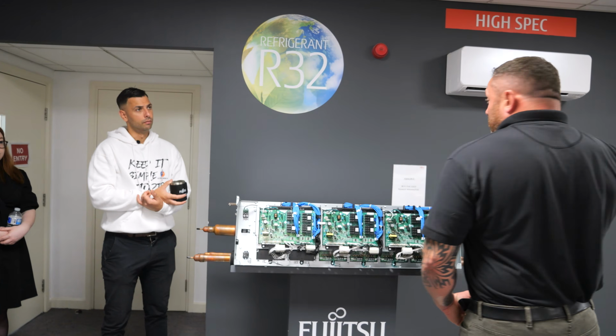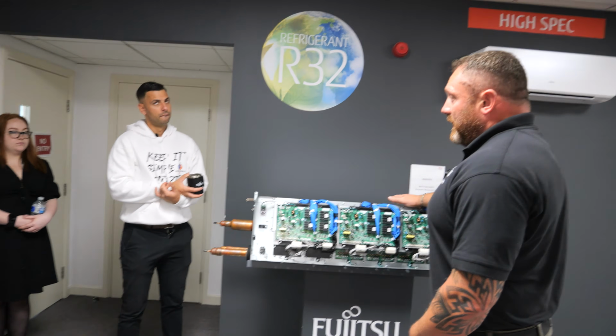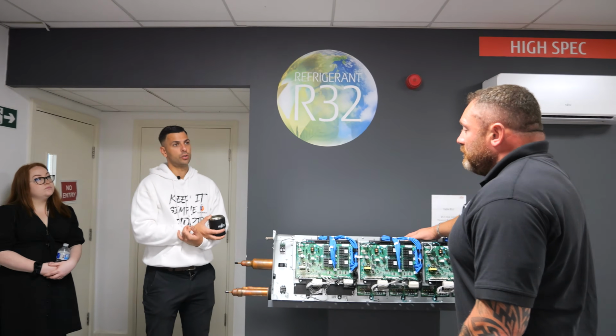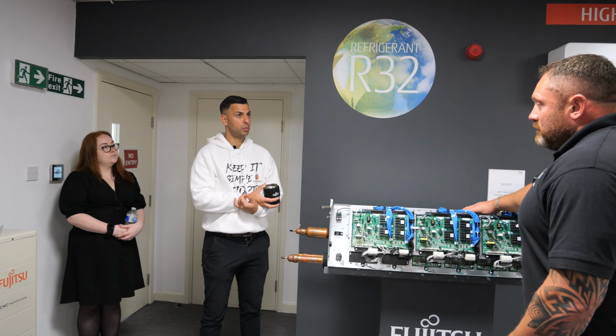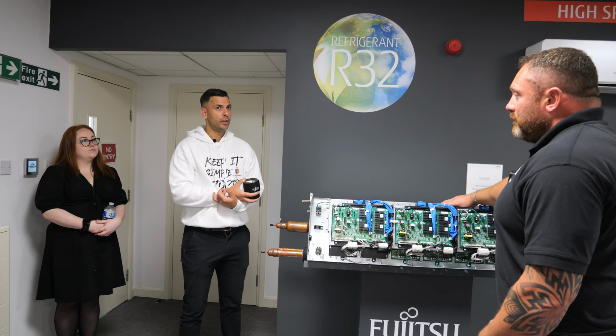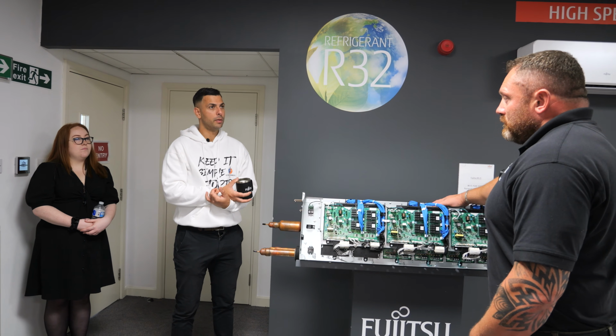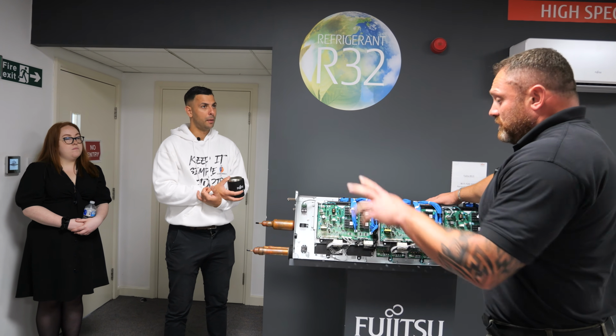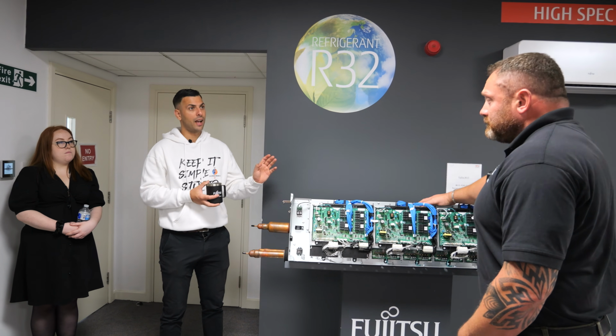The Eco unit doesn't work with it, that's basic, literally infrared. So if I've got a comms room with 2 wall mounts that have failed, and I put in 2 Fujitsu wall mounts with this controller, I don't even need to speak to the client about programming them on a timer. It can just be set up, put a lead-lag timer in, and it's all done from the controller.